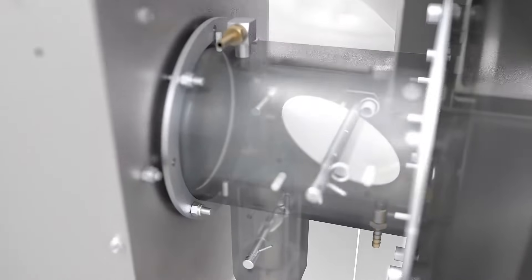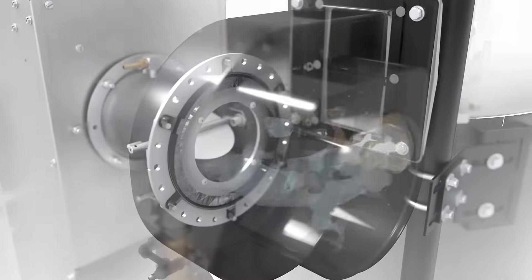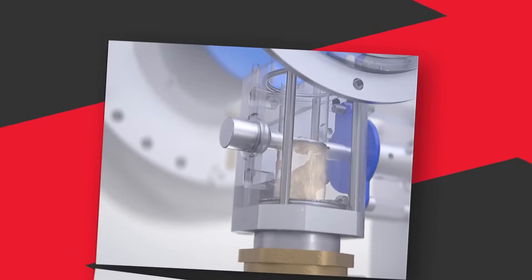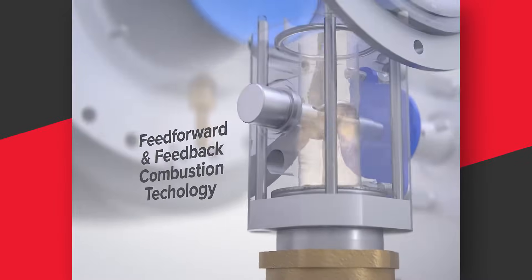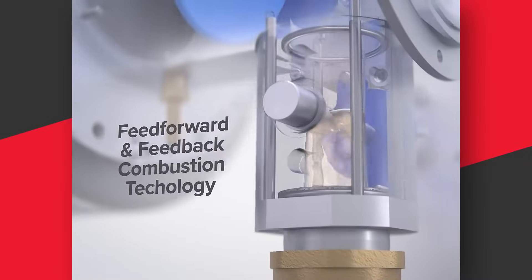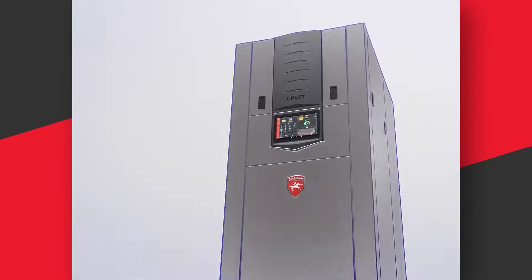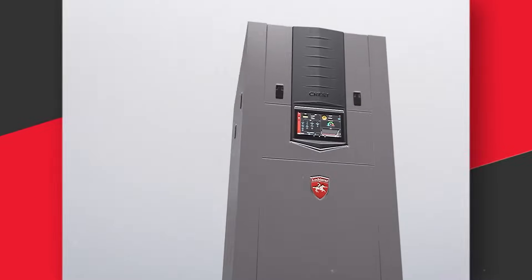Trimming is the balancing of the air-to-gas ratio to reach the desired O2 target. Our feed-forward system includes barometric pressure and supply air temperature sensors that read the environment and adjust the air and gas dampers to supply the optimal air-fuel mix.